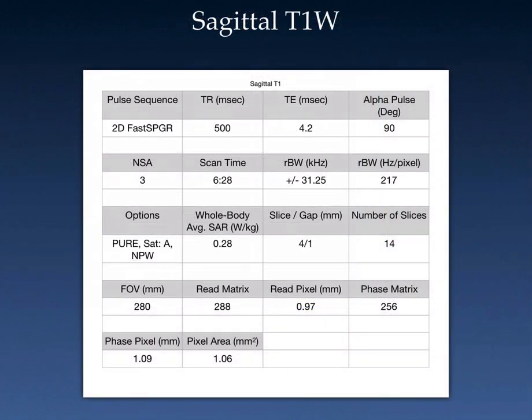For the diagnostic sequences, we'll start with the sagittal T1 weighted sequence. We chose a 2D fast SPGR sequence on a GE — a version of their spoiled gradient echo sequences. TR is 500 milliseconds, TE of 4.2, 90-degree flip angle, three signal averages, giving a scan time of 6 minutes and 28 seconds. We used receiver bandwidths of plus or minus 31 kilohertz (217 hertz per pixel). Imaging options used on all sequences included PURE for image intensity correction, an anterior SAT pulse, and GE's no phase wrap anti-aliasing oversampling option. The whole body SAR was only 0.28 watts per kilogram.